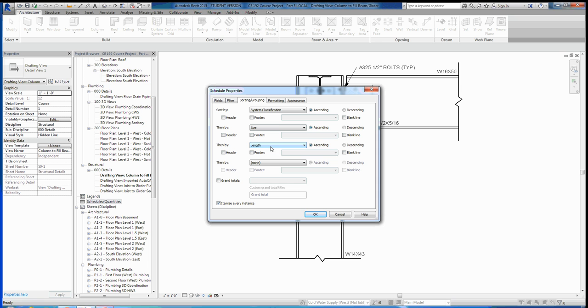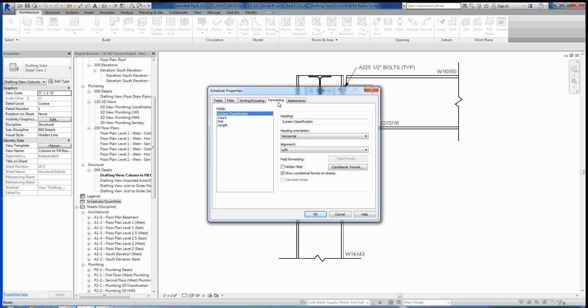The last thing we need to do is uncheck this box right here that says itemize every instance. What that does is it makes it so that every single pipe in the project is going to be displayed in its own row. If we have identical pipes though, there's really no point in itemizing every instance. So if we uncheck that, let's say if we have five pipes that are hot water supply, half inch, and exactly five and a half feet, we'll just have all that in one row with a count number of five. I'll let you guys play around with formatting and appearance if you want to. The standard Revit settings for those are just fine though, so I'm not going to worry about that. So we'll hit OK.